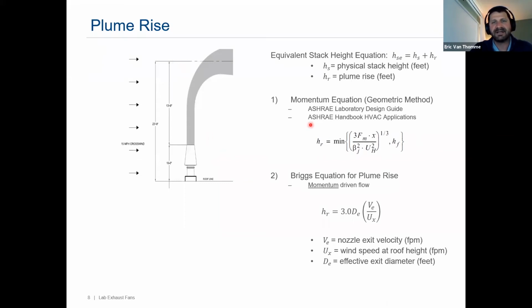The ASHRAE Laboratory Design Guide and the HVAC Handbook for applications have really two different methods for calculating this plume rise. Each manufacturer kind of uses their own or can produce both. We can produce both as part of our resultant submittal data, but they use either this momentum equation or this Briggs equation. Both are fairly common and have been ASHRAE tested and approved, and so both are utilized in producing and comparing one lab fan to another.